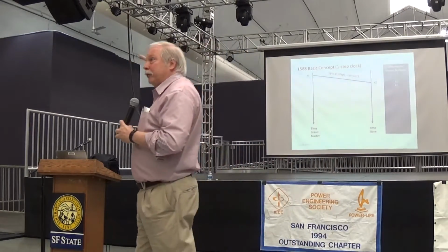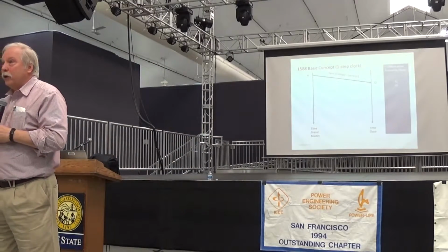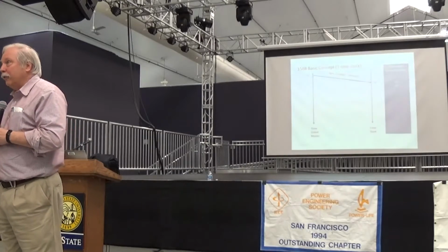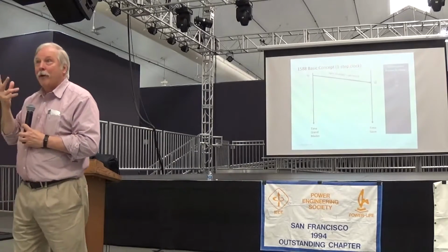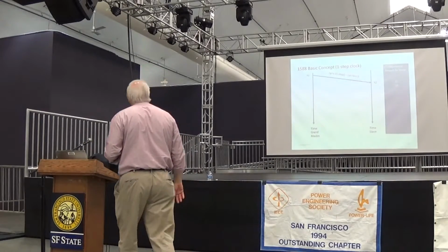Today, there is a 36-second difference between TAI and UTC. So it's a simple calculation, but it has to be done. The message that gets sent out from the Grand Master contains what the offset is at an instant in time. So that is part of the message communicated from the Grand Master clock.